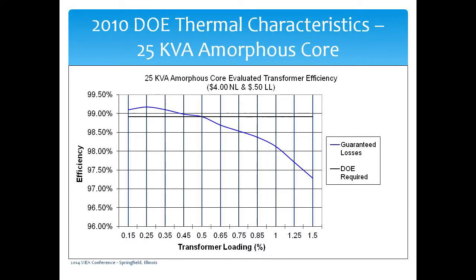But one difference I wanted to point out between the amorphous, because the amorphous at that 50% load starts to taper off. Of course that allows you to put in the amorphous cores, which are actually larger, but the coil becomes smaller. So there's a trade-off on it. So if you run over 50% load, I'd probably tend to go with more of the silicon type designs than the amorphous, because the amorphous is more backloaded. Usually it's going to be more backloaded on the winding side, the conductor, rather than the core side.